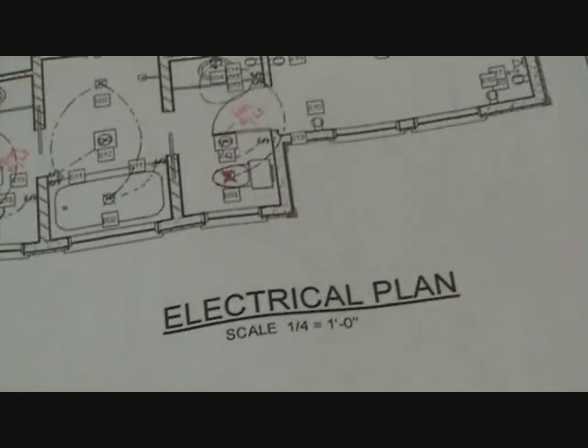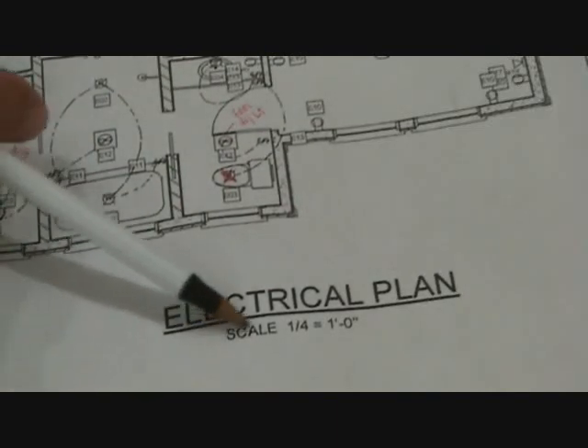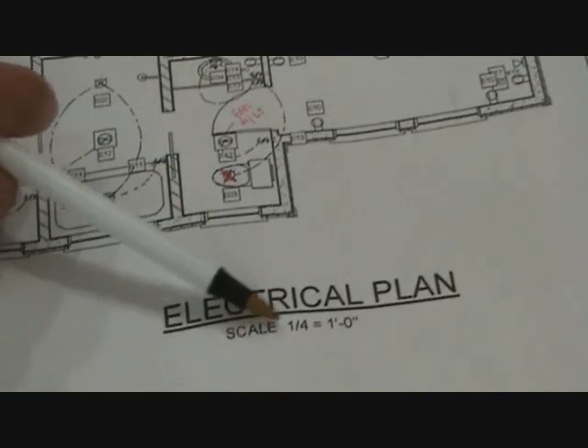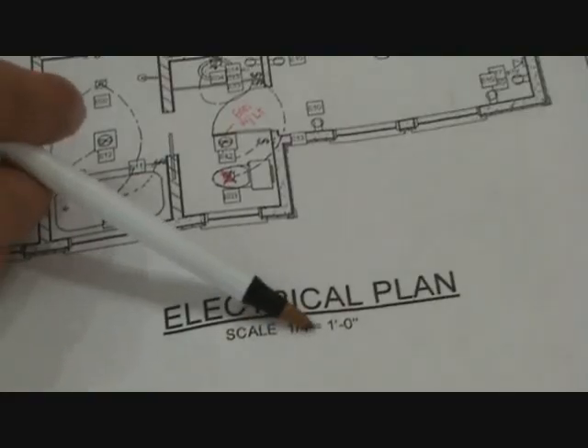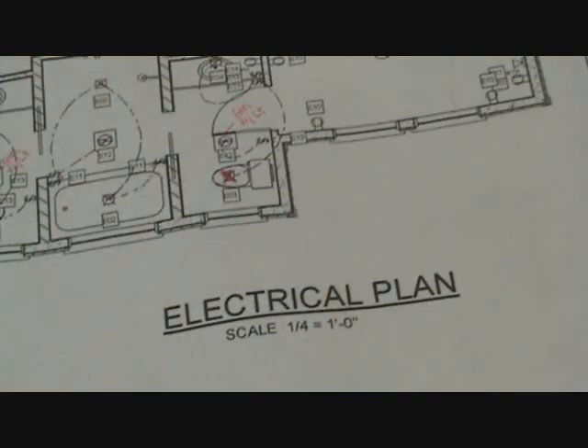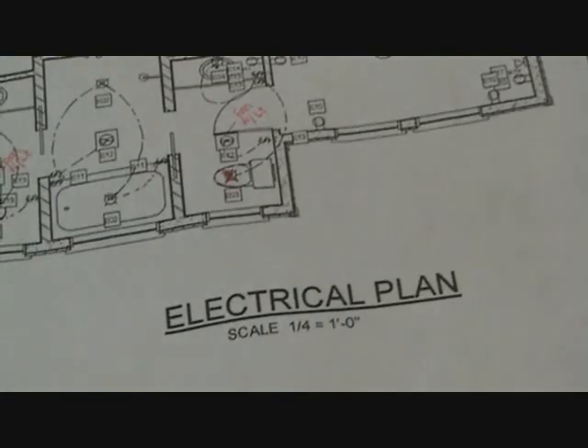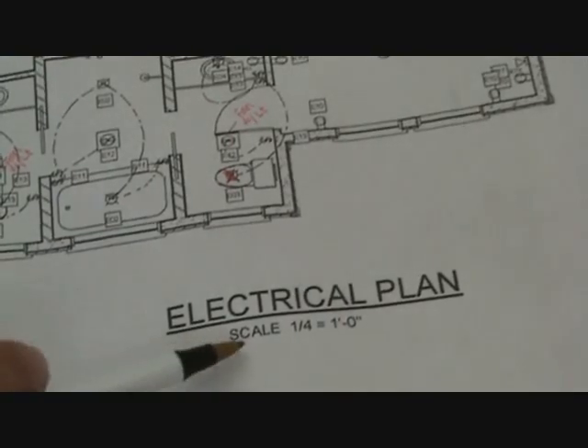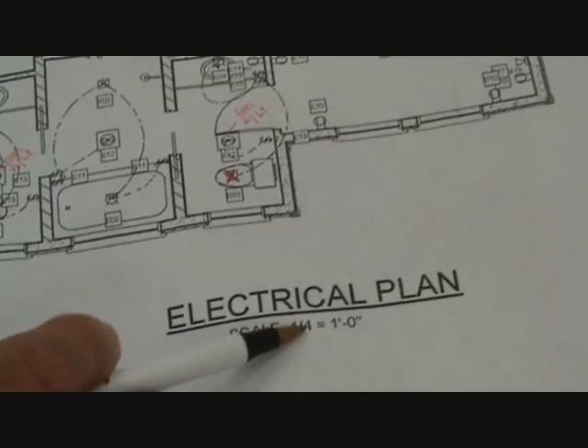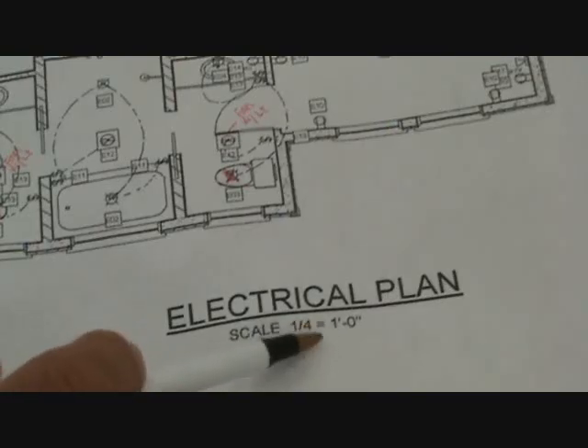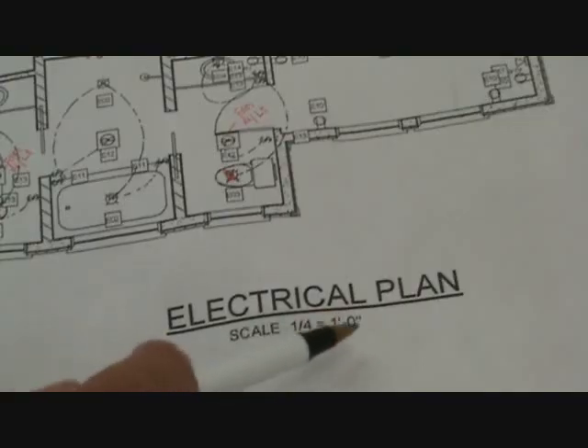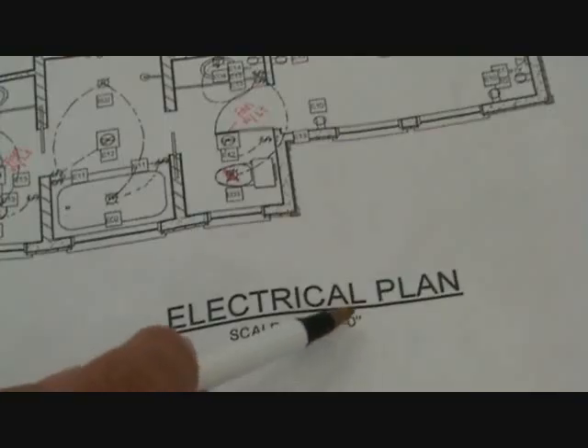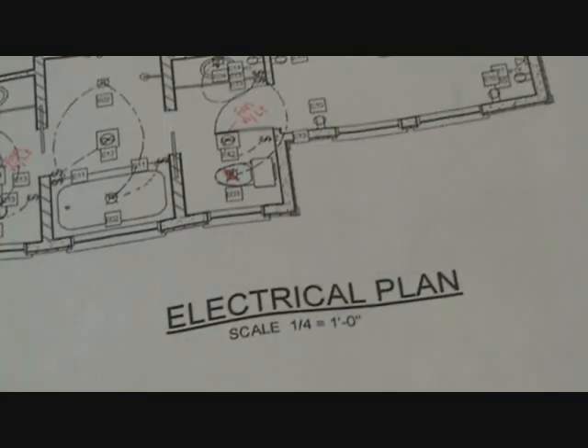This is the electrical plan. And see, it has a scale. So you look at that. It says scale, and that says quarter, equals, and then some other gibberish. So what does that tell me? That tells me they're meaning a quarter inch equals one, and the little line above it means 1 foot dash zero, and the two lines mean inches.